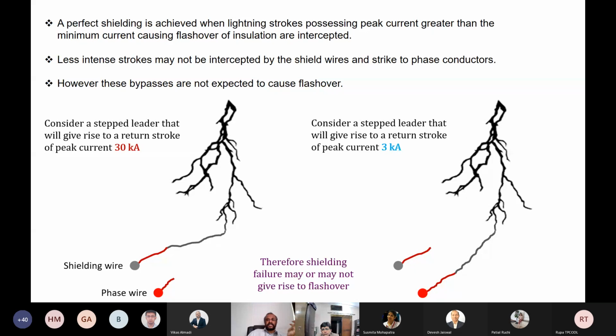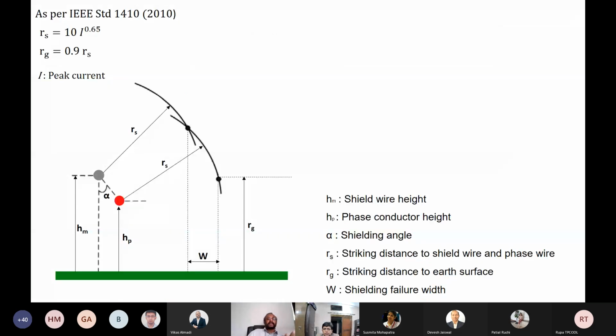So therefore, shielding failure may or may not give rise to flashover. Now, as per IEEE standard 1410, consider the rolling sphere radius of the shielding wire and a live wire in this way, say that it is RS. Then you can see that if a step leader, the purple colored lightning, comes along the sphere which has a radius RS from the shielding wire, then it will definitely be intercepted by the shielding wire. Okay, hope that you understand that.